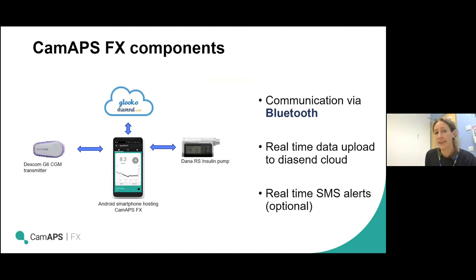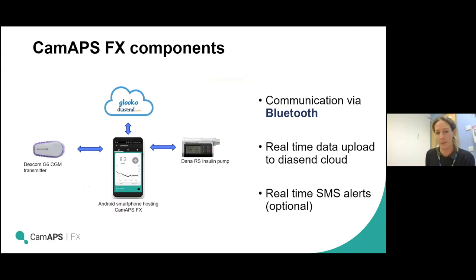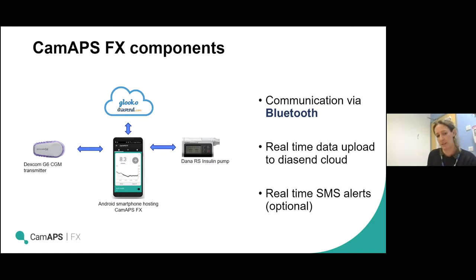The specific components of the CAM APS FX closed loop system: the glucose sensor is called a Dexcom G6 continuous glucose monitor or CGM — about an inch and a half long, worn flat against the skin, normally on the tummy or upper arm. The Dana RS insulin pump has a piece of plastic tubing connecting to the child's body. The control algorithm is found as an app on a standard Android smartphone — you can see the green bubble icon — that takes you into the CAM APS FX app.